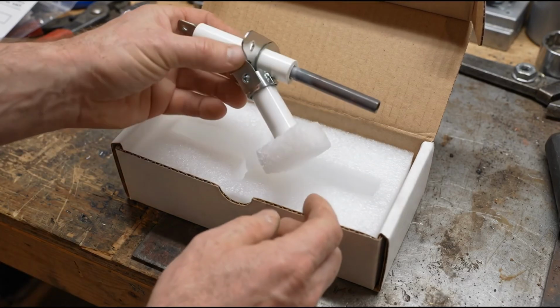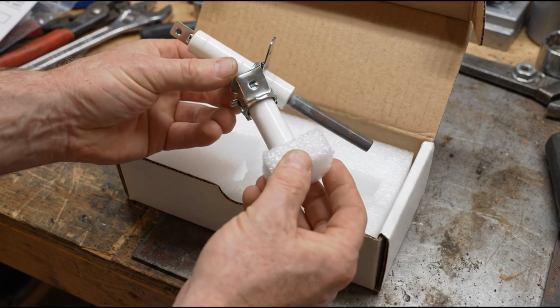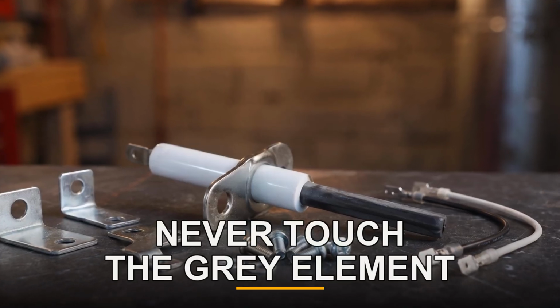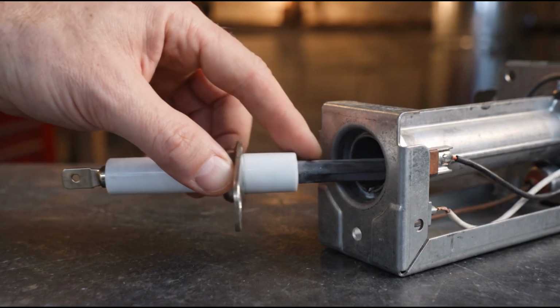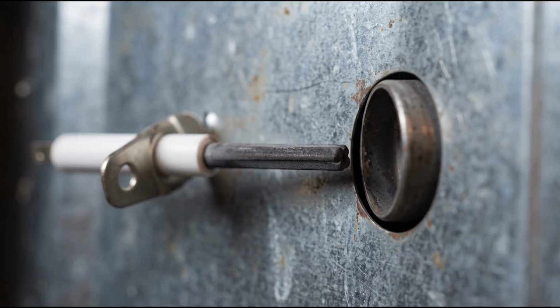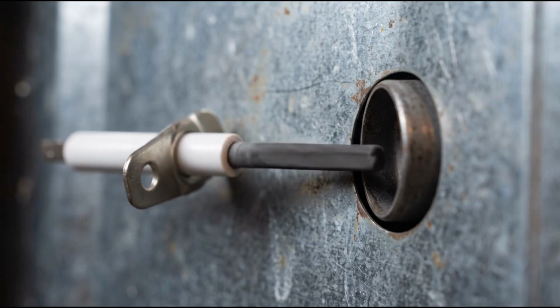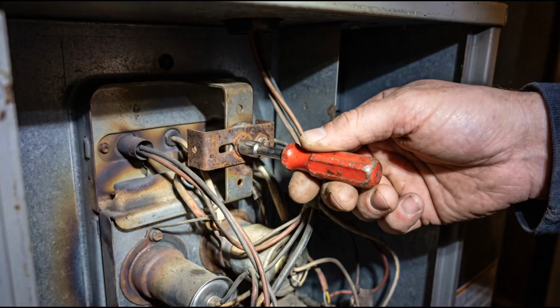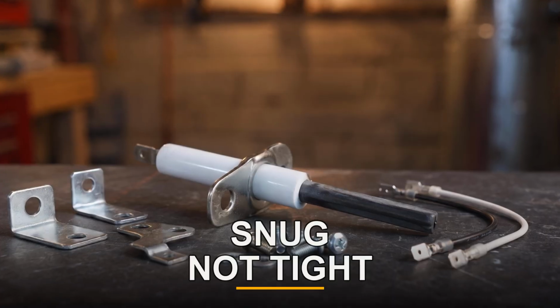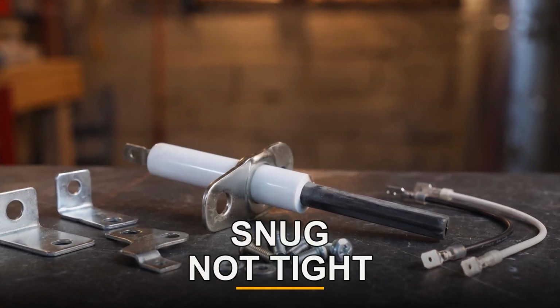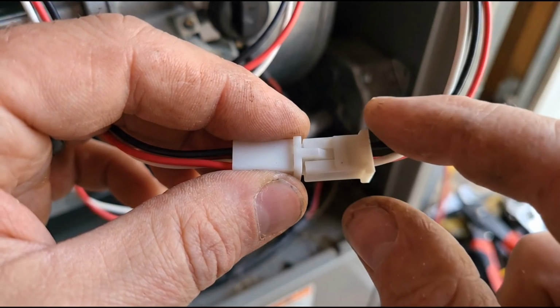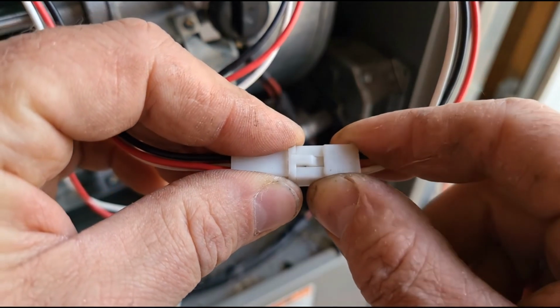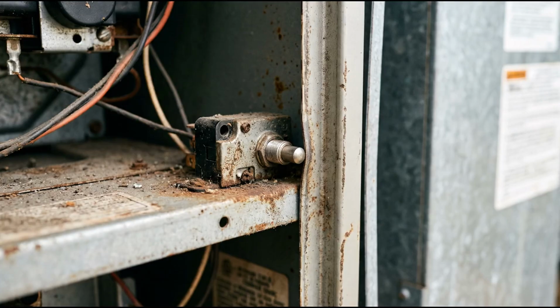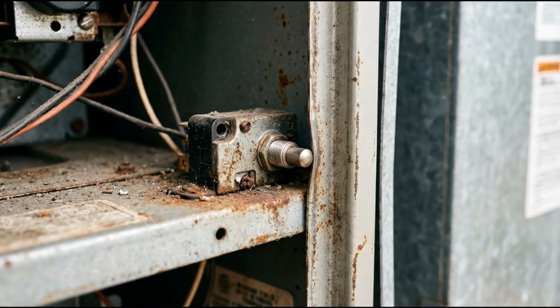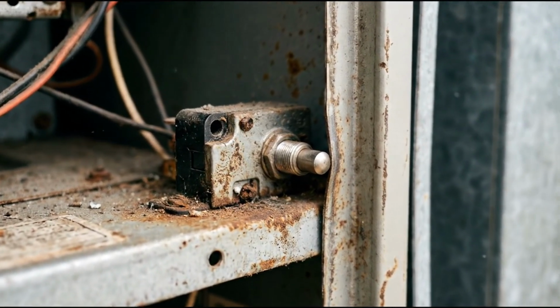Hold it only by the white ceramic base or the bracket, never by the gray element. Set it in exactly the way the old one sat, with the tip near the burner but not touching any metal. Snug the screw. Snug, not gorilla tight. This is ceramic. Plug in the connector. Door back on. Most furnaces will not run with the door off. There is a safety switch under it.